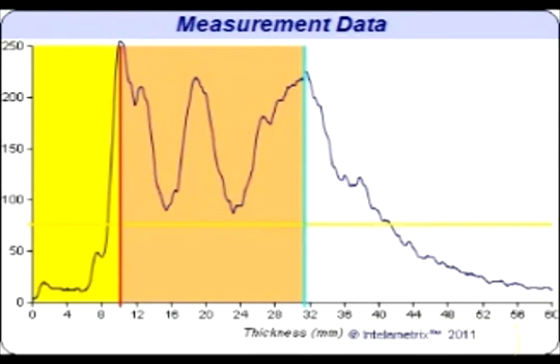In the waist, the first peak is often a fascia layer which divides the subcutaneous layer into a superficial fat layer and the deep fat layer. For elite or low body fat individuals, the fascia layer merges or gets very close to the fat muscle interface, and in that case the software will take the first peak as the fat muscle interface. However, for individuals with thick waist fat layers, the software will often identify the second strong peak as the fat muscle interface. This fat structure is more evident in waist measurements but can appear at other measurement sites for obese individuals.